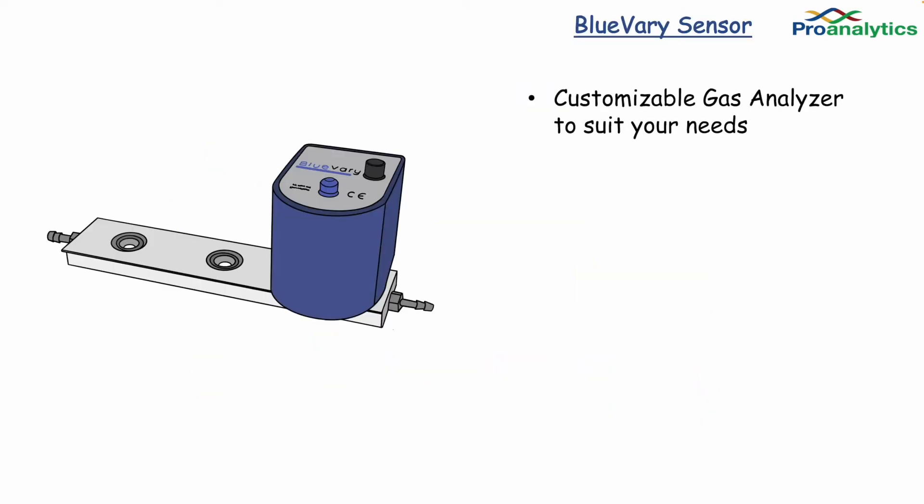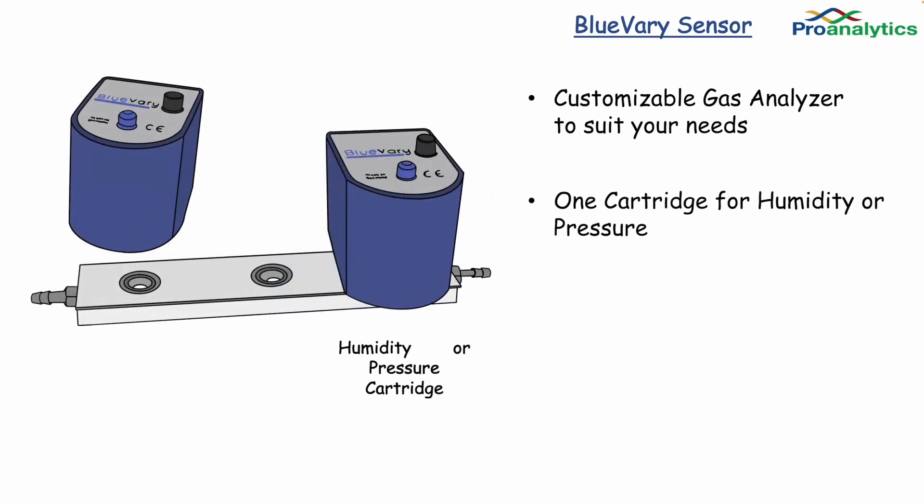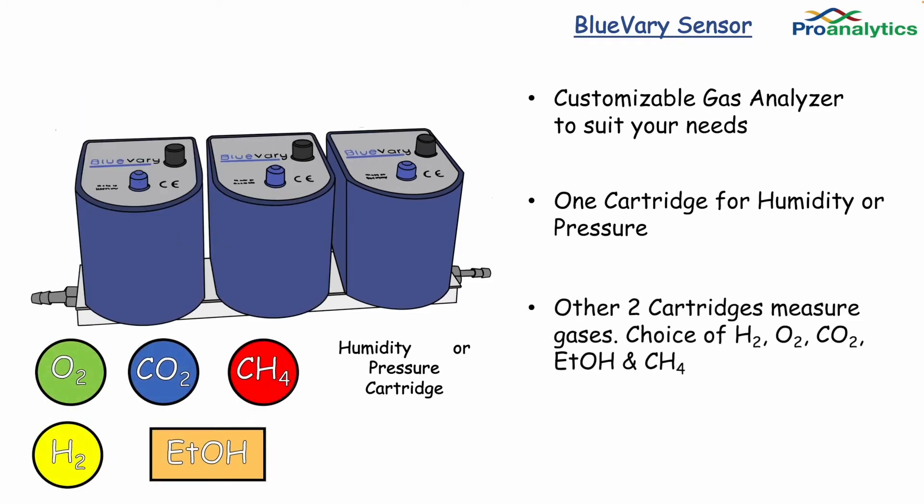BlueSense also makes the BlueVary sensor, which is tailored to meet your off-gas needs. The BlueVary has three plug-in positions for sensor cartridges. One cartridge is dedicated for pressure or humidity, while the other two cartridges can be used for oxygen, carbon dioxide, methane, hydrogen, or ethanol.